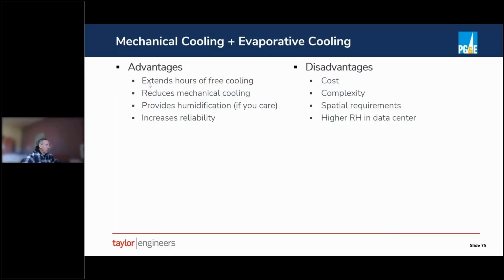So what is the advantage of this system? It can extend the hours of free cooling with the evap cooler. Almost no mechanical cooling required. Evap cooling provides humidification, basically as a freebie, if that's important. We've argued that it isn't important, but a lot of data centers still insist on it. It gives you some added reliability, since you basically have three sources of cooling: mechanical cooling, economizer cooling, and evaporative cooling. The disadvantages: you're adding some cost by having those three sources. It can get complicated trying to stage the different options. Spatial requirements.